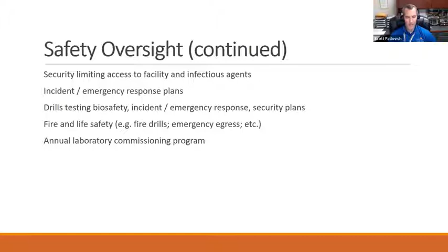And then we have what's called an annual laboratory commissioning program. So when we set this laboratory up, we have to shut it down once per year to make sure that all the equipment is working properly, the HVAC system is working properly, all of the containment devices are certified, the autoclave that decontaminates all the waste coming out of the facility is working properly and properly sterilizes all that waste. All of these things are done during the annual commissioning to ensure that the laboratory is functioning as designed. And this is a requirement, by the way, of the BMBL.